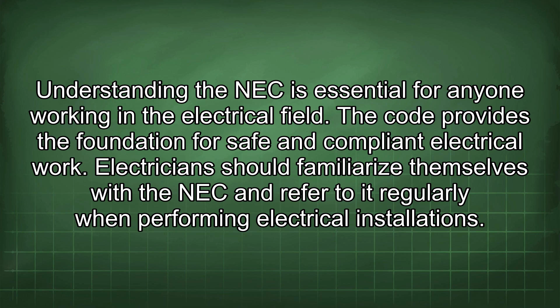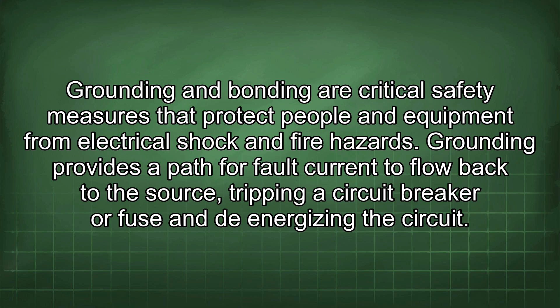Grounding and bonding are critical safety measures that protect people and equipment from electrical shock and fire hazards. Grounding provides a path for fault current to flow back to the source, tripping a circuit breaker or fuse and de-energizing the circuit. Bonding connects all metal parts of an electrical system together, creating a low impedance path for fault current to flow. Grounding and bonding are covered in Article 250 of the NEC.